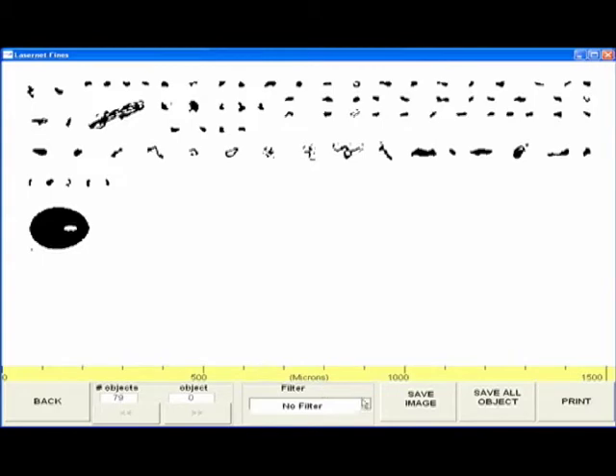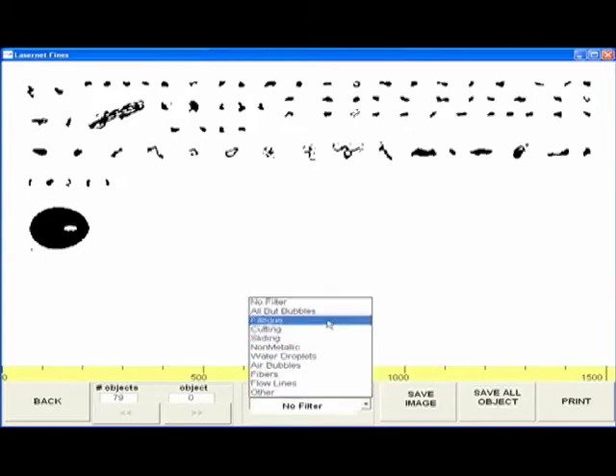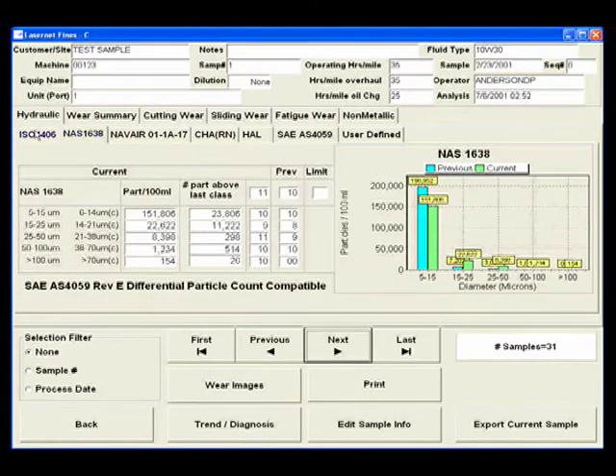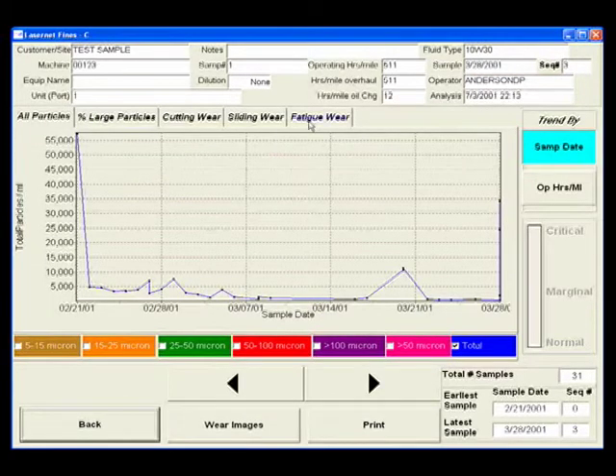Specialized software automatically sorts the particles into five categories, something which no other particle counter on the market is capable of. This technology enables the LNF to more accurately determine the particle concentration as well as classify the particles according to type of wear and size.